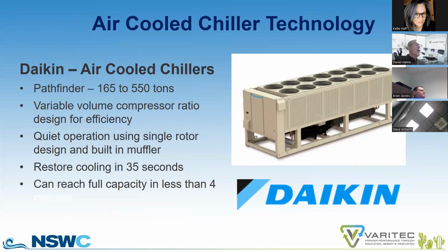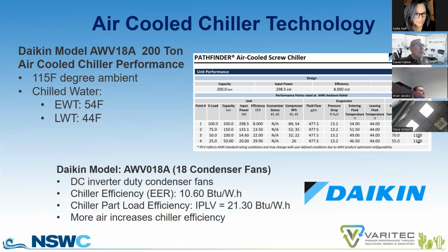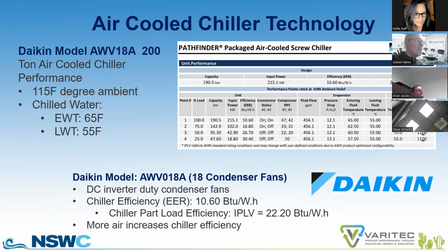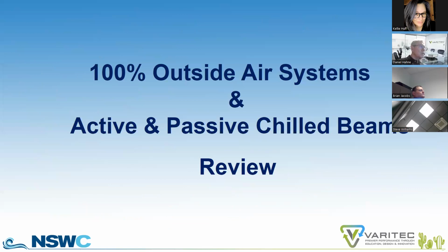So what does that mean with regard to chiller technology? Well, working with Daikin, we did an evaluation on the new air-cooled Pathfinder chillers, and we found out that the EER of a chiller supplying 44-degree chill water in our design environment with 18 condenser fans has an 8.0 EER. If you actually provide 55-degree chill water, your EER and IPLV levels bump, so you get added chiller efficiency by supplying warmer chill water temperatures, and you can design the DX DOAS to a low enough dew point supply air condition where you can provide tight building latent control as well.